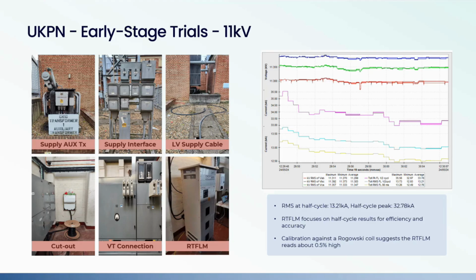The results were calibrated, and it suggested that the RTFLM measured the fault level 0.5% above the calibration device. So even from the outset, this site gave us confidence that the system could deliver credible, stable measurements, setting the foundation for the wider trials that followed. Can move to the next slide, Ed.